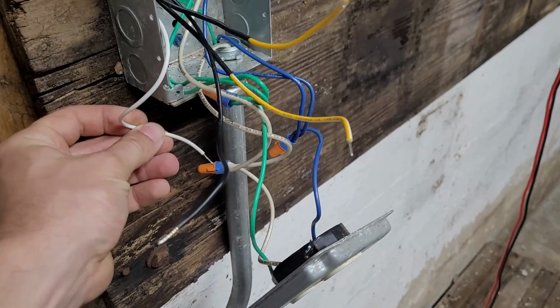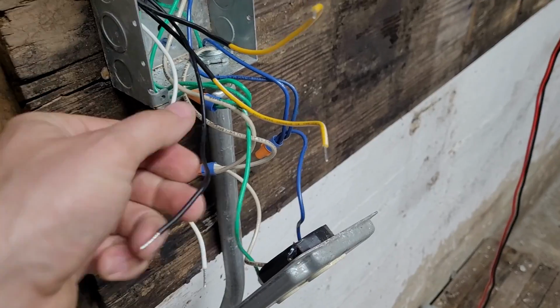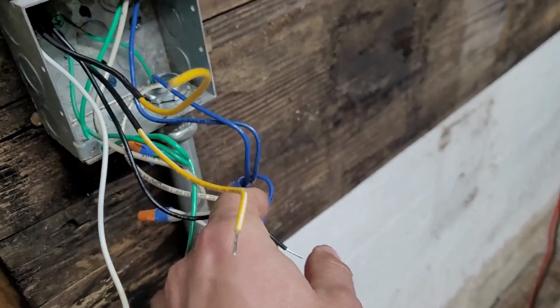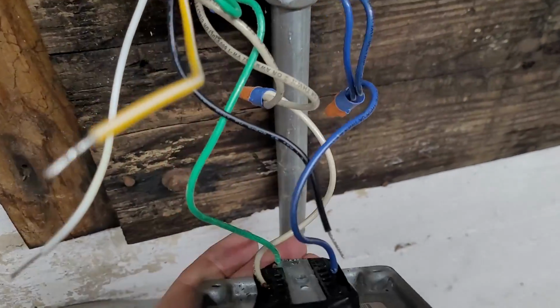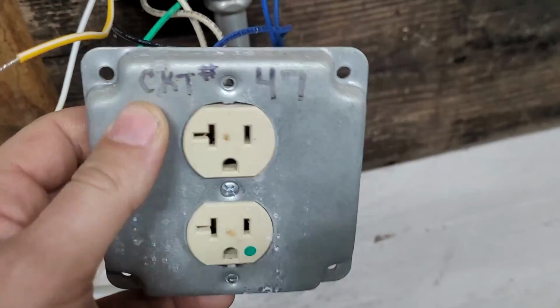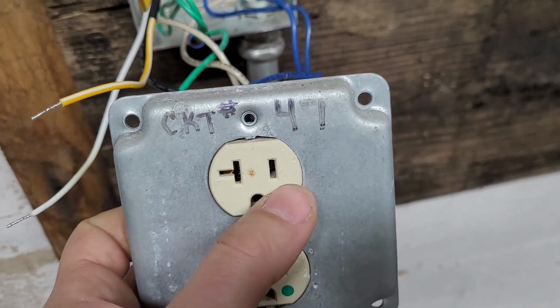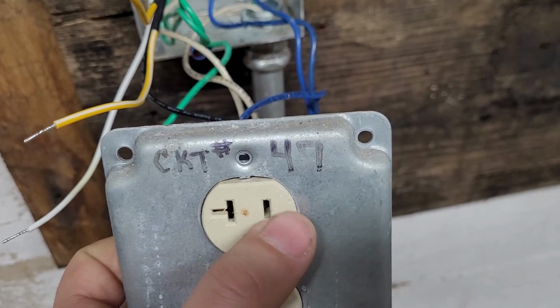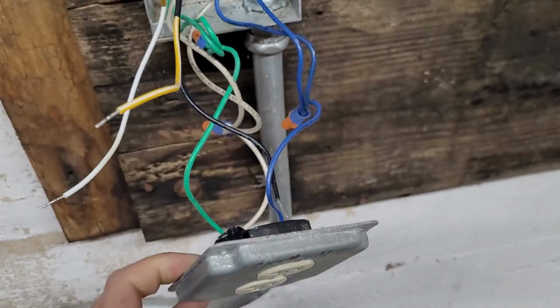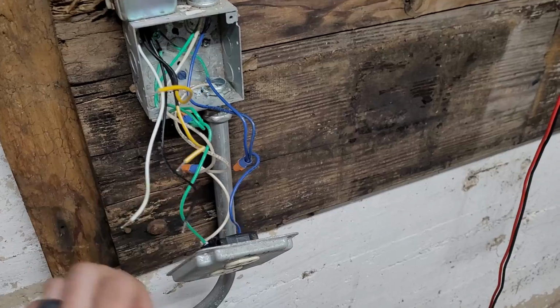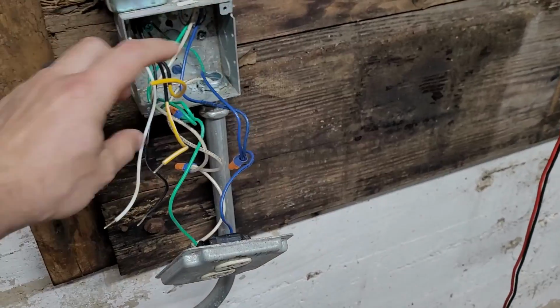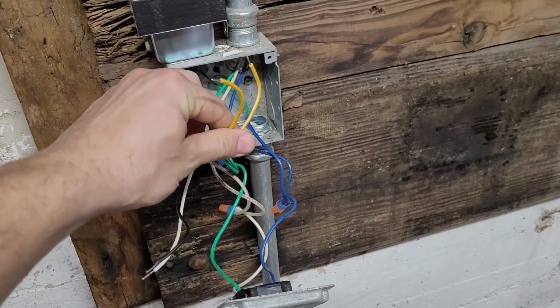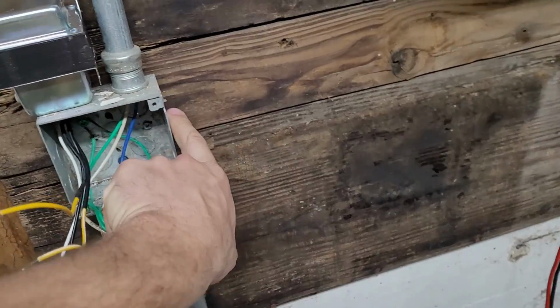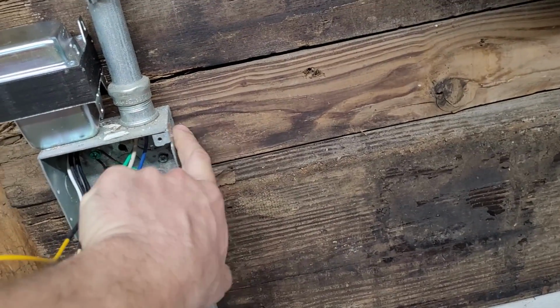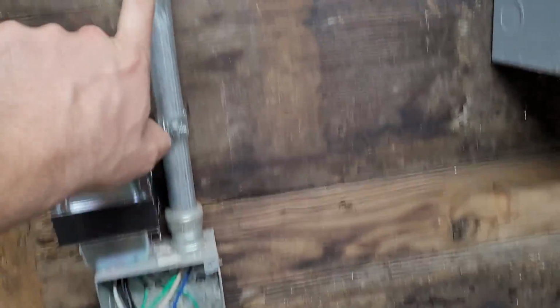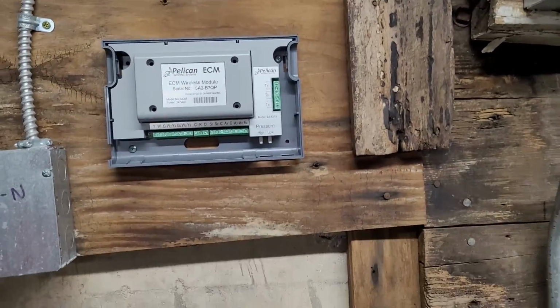So I'll just use white in this wire nut with these neutrals and black in this wire nut with these blues. The other way you can tell is that the hot will be with the smaller, this one's small and this one's big. The big one is the neutral, the small one is the hot. So once I get the high side wired in, I'll put the receptacle cover back on. I'll have the low voltage run out, maybe knock out another knockout and put a little bushing there. Run the low voltage up and over to the plant controller.